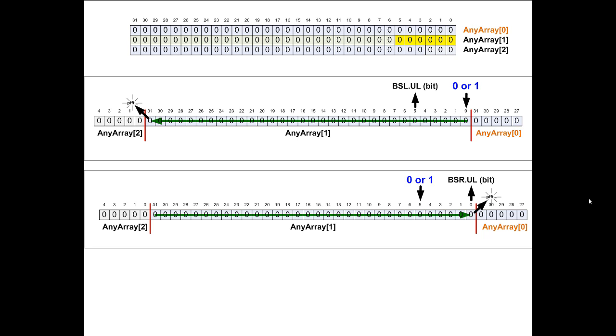Now that value that's in bit 5, when it gets unloaded to the unload bit, it also shifts to bit 6. And as you keep executing the bit shift left, pulling in new values at 0 and unloading them at 5, they don't disappear. Instead they go to 6, 7, 8, 9, all the way down to the end.